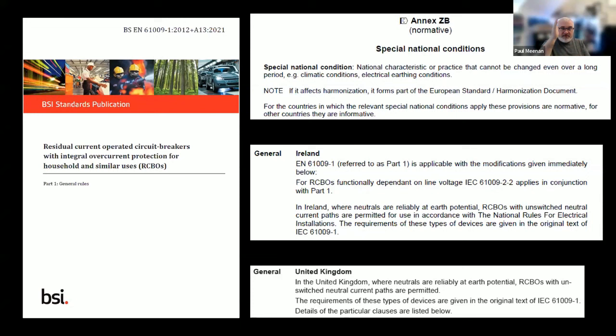That's a combined MCB and RCD with overcurrent protection. It has some special conditions that say in Ireland, 61009s dependent on line voltage can be used. You can use unswitched neutrals in the UK, where the neutral is reliably at earth potential; RCBOs with unswitched neutral are permitted. But what if you don't have that? What if you have an installation with single pole devices, diverted neutrals and a rise in neutral current? Then surely you don't potentially have a reliable earth potential. So it's worthwhile looking through your standards to see if there are any national conditions.